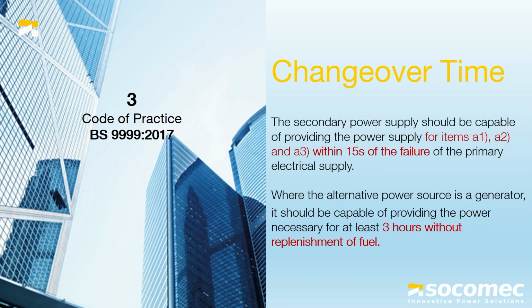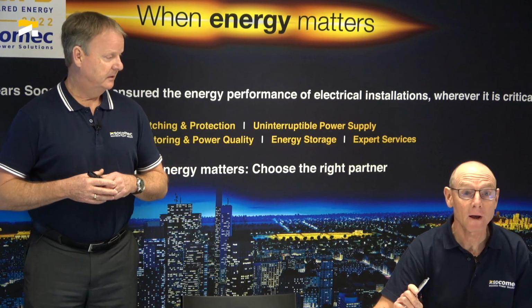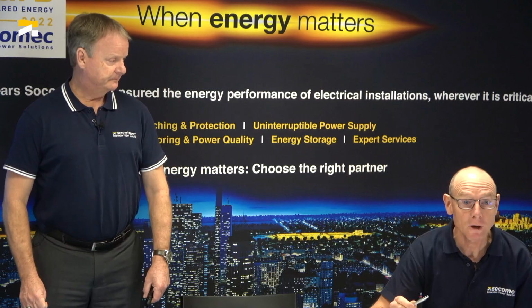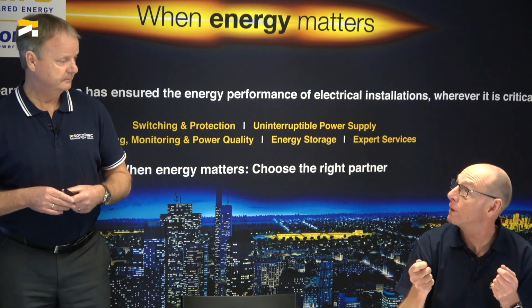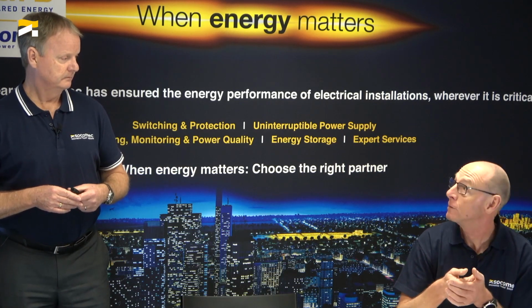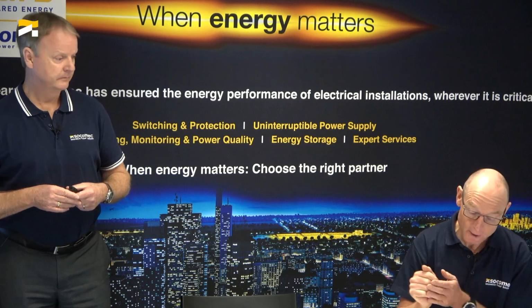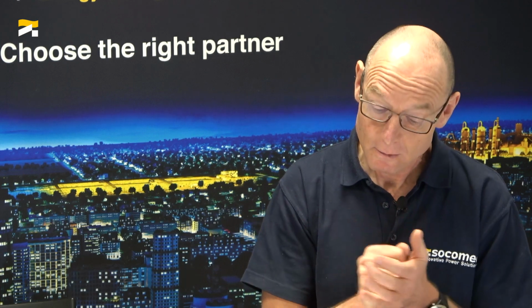These relate to specific items. A1 is powered smoke control - if there is an event where smoke is given off, how you can evacuate that smoke from the building. A2 is about fire and rescue communication - if fire staff have to attend the building, how they can communicate within it, and we need to maintain those communications and equipment. A3 is about general firefighting equipment. So these are all part of this.